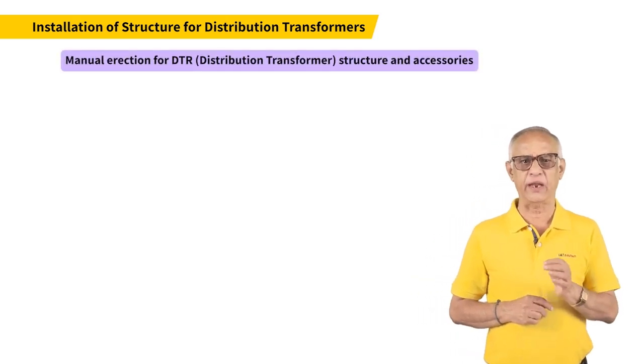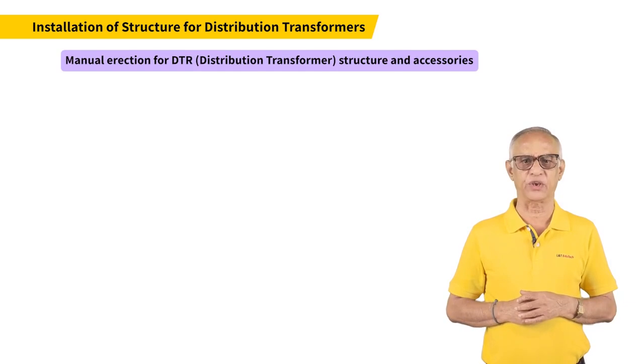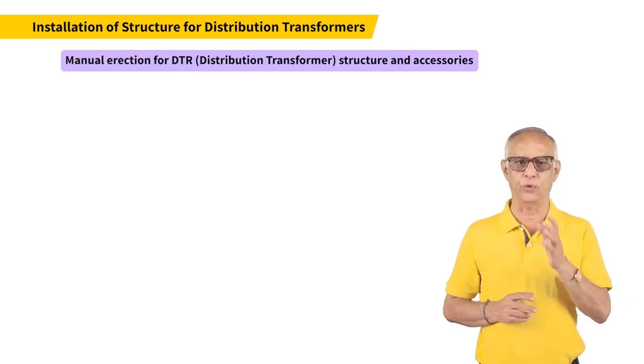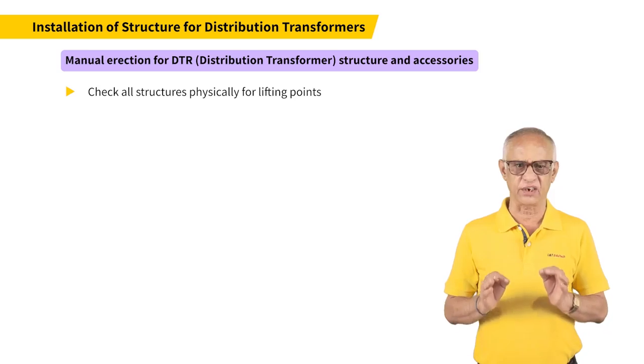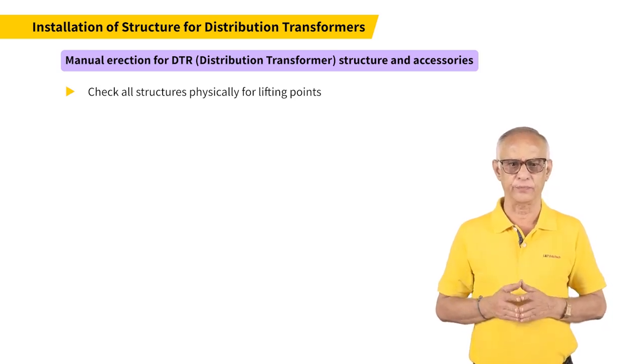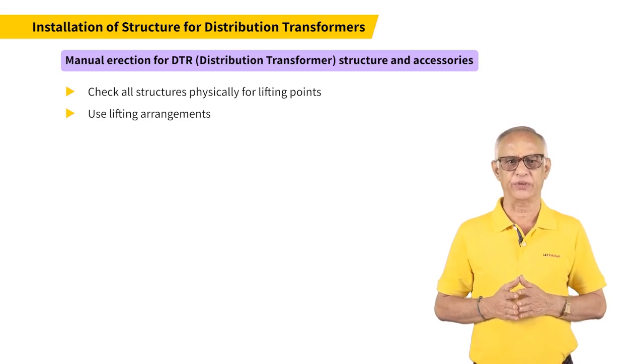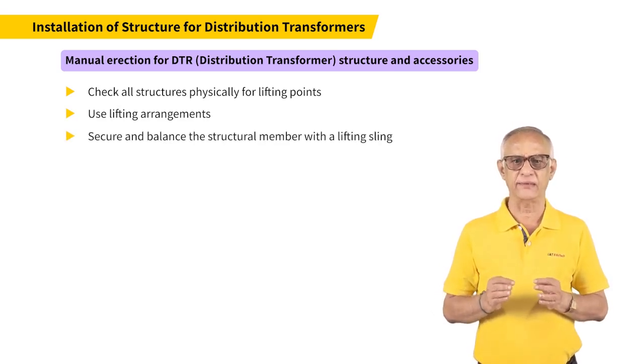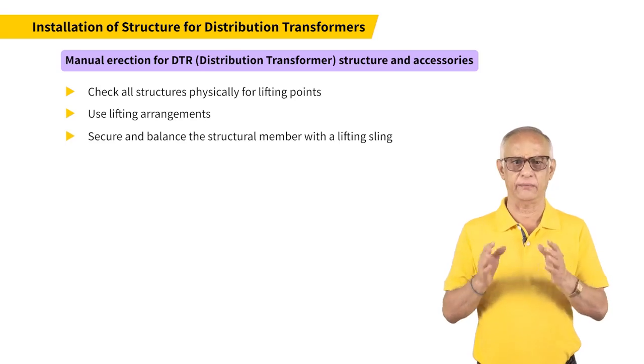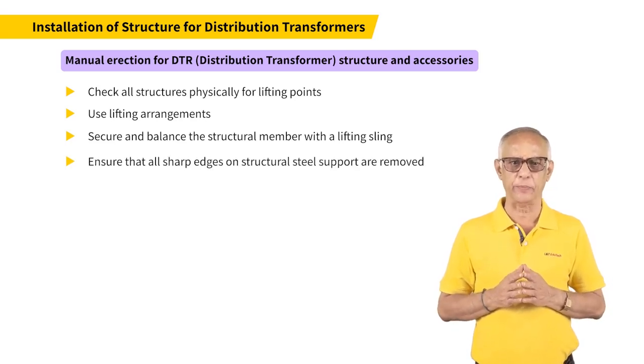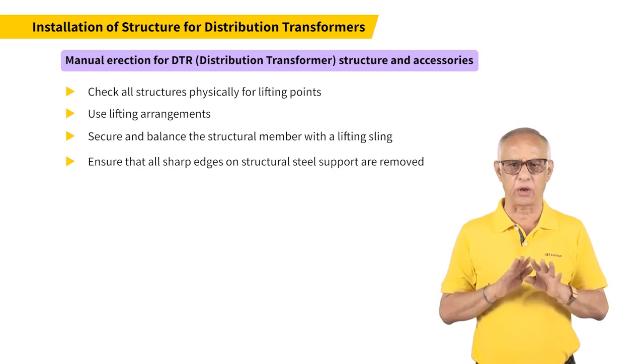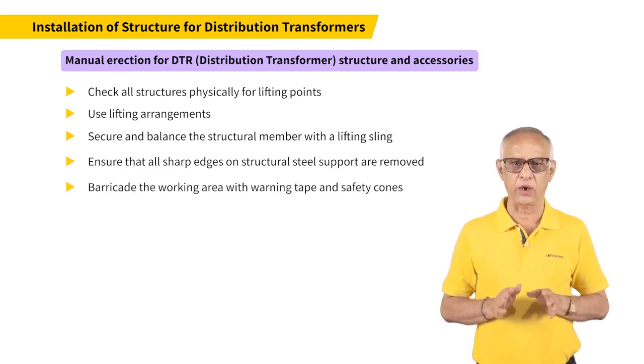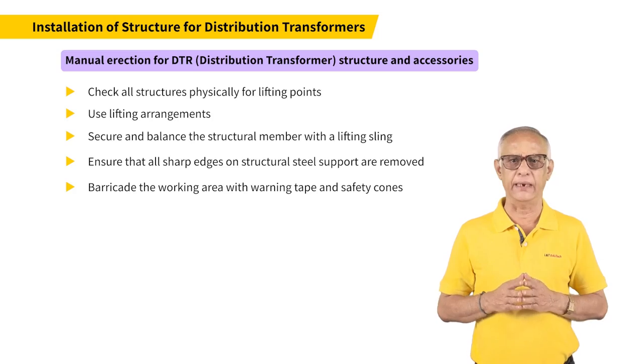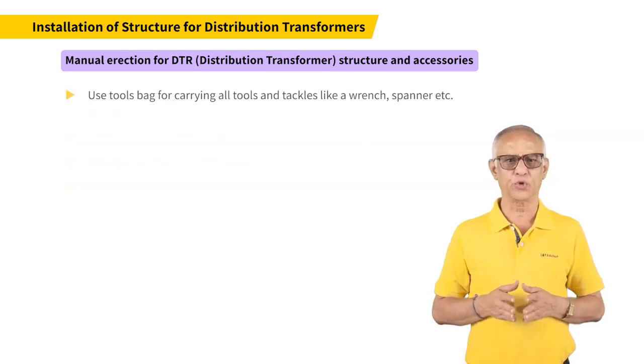The steps for manual erection of distribution transformer structure and accessories are as follows. Check all structures physically for lifting points. Use lifting arrangements. Secure the structural member with the lifting sling. Ensure that all sharp edges on structural steel supports are removed. Barricade the working area with warning tape and a safety cone. Use a tools bag for carrying all tools and tackles like a wrench, spanner, etc.